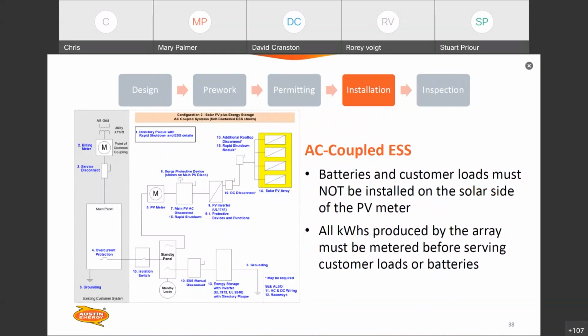Cool. Thanks, Rory. So energy storage systems, AC coupled energy storage systems. Those are the only ones that we allow in our territory. So the batteries and any customer loads must not be installed on the solar side of the PV meter. So any situation which would send current back through the solar meter is not allowed. So all you want on the solar side of the solar meter is the solar production equipment itself.